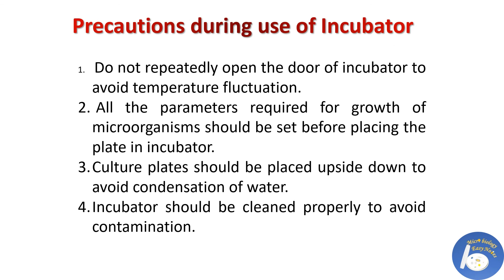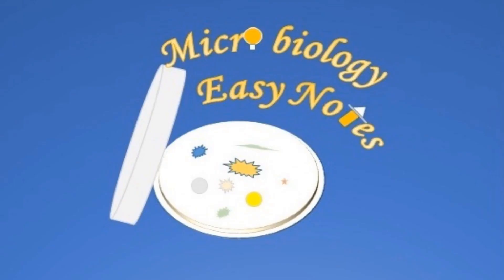Precautions during use: do not repeatedly open the door of the incubator to avoid temperature fluctuation. All parameters required for growth of microorganisms should be set before placing the plates inside. Culture plates should be placed upside down to avoid condensation of water. The incubator should be cleaned properly to avoid contamination. Thank you for watching.